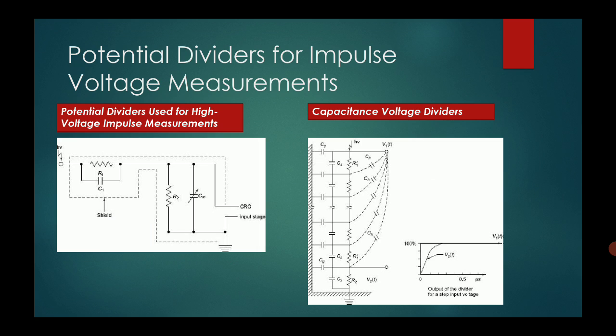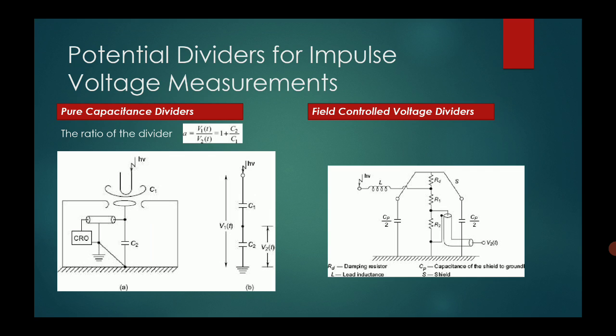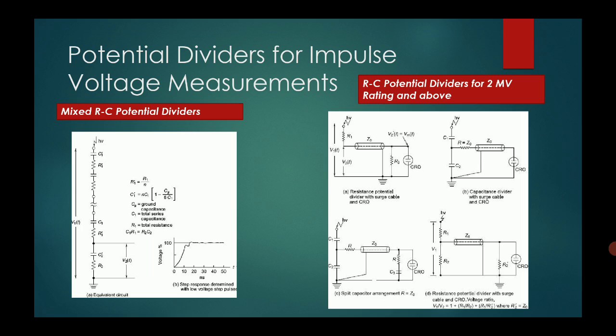There are other potential dividers for impulse voltage. One is the potential divider for high voltage impulse measurement, and this is the schematic diagram. The other is the capacitance voltage divider. As with the resistance dividers, we have capacitance voltage dividers. We can also have a pure capacitance divider with the voltage ratio given as follows. Then we have a field controlled voltage divider, with the schematic diagram given below. Potential dividers for impulse voltage measurements also include mixed RC potential dividers, where we have both R and C for the potential division, and RC potential dividers with a 2 megavolt rating and above.